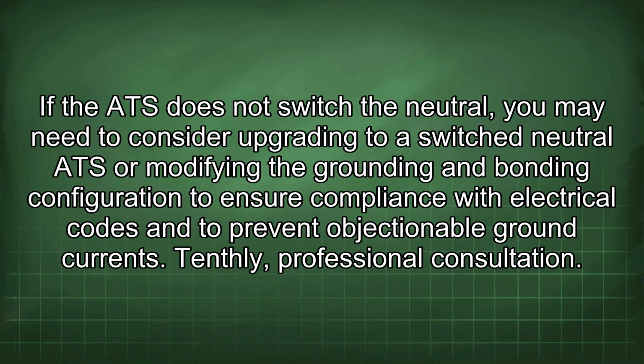If the ATS does not switch the neutral, you may need to consider upgrading to a switched neutral ATS or modifying the grounding and bonding configuration to ensure compliance with electrical codes and to prevent objectionable ground currents. Tenthly, professional consultation.